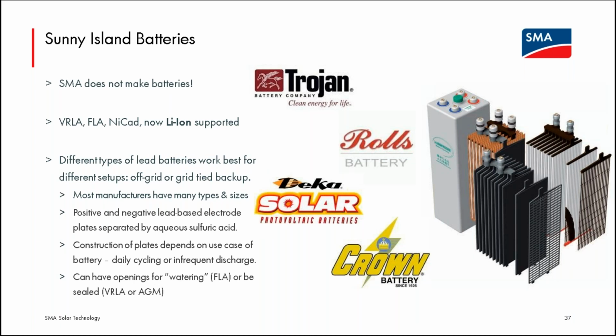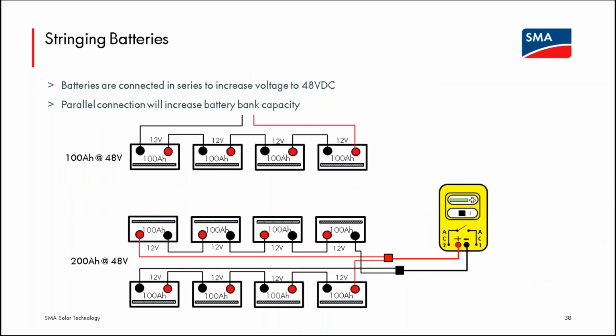We don't have an approved list for lead acid batteries for the Sunny Island. All we really require is that nominal voltage of 48. It is very nice that there are many, many reputable manufacturers and they build batteries for different use cases. Off-grid would be daily cycling, whereas battery backup would be much more infrequent cycling, but it might be deeper. And the manufacturers can build the electrode plates to actually fit either of those use cases.